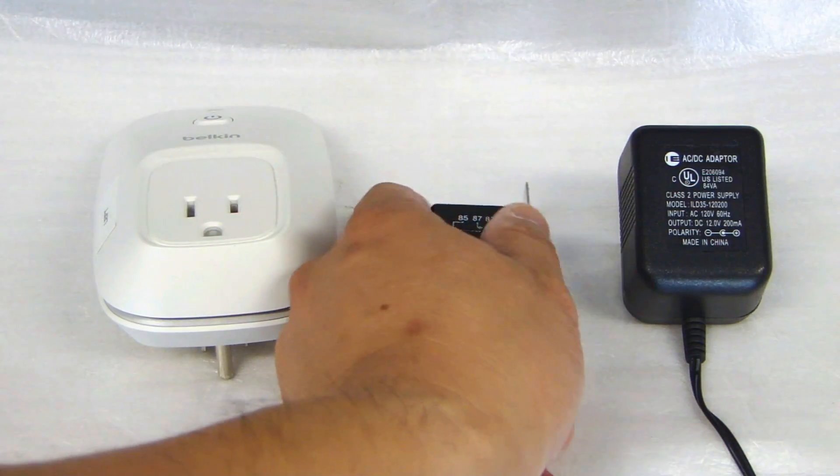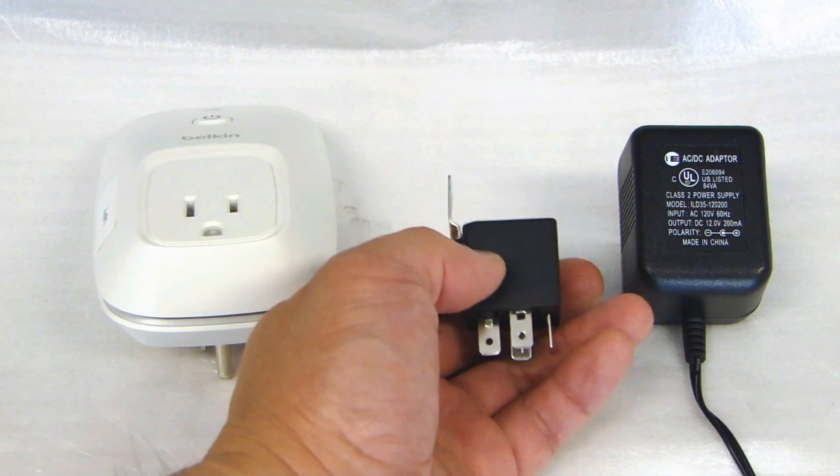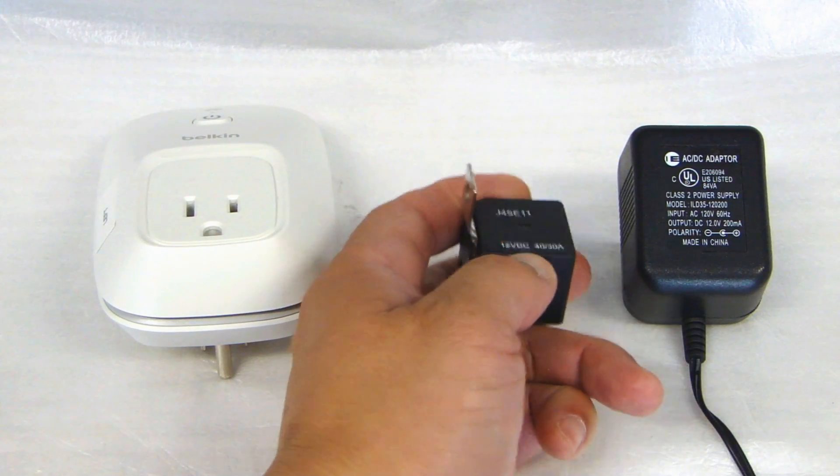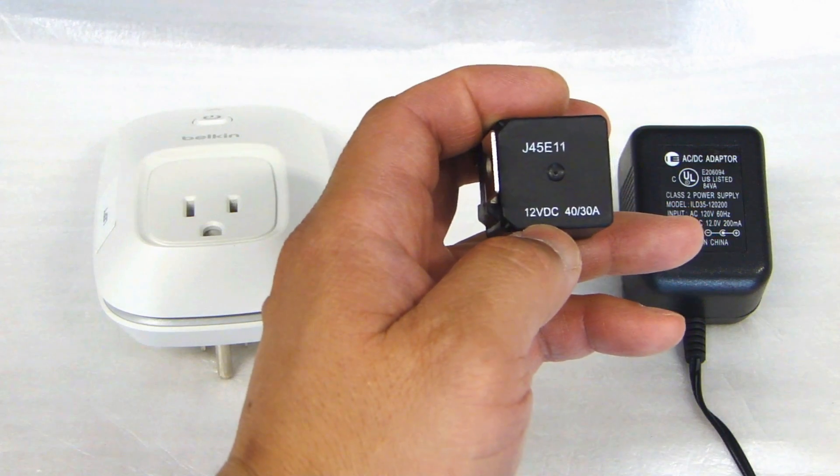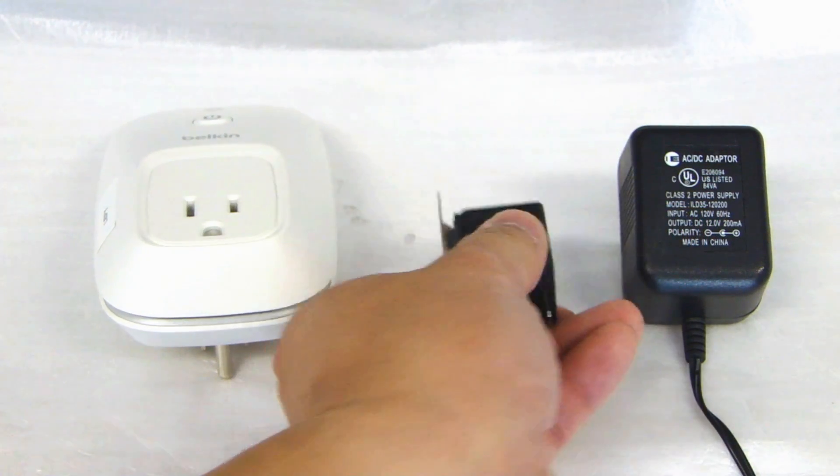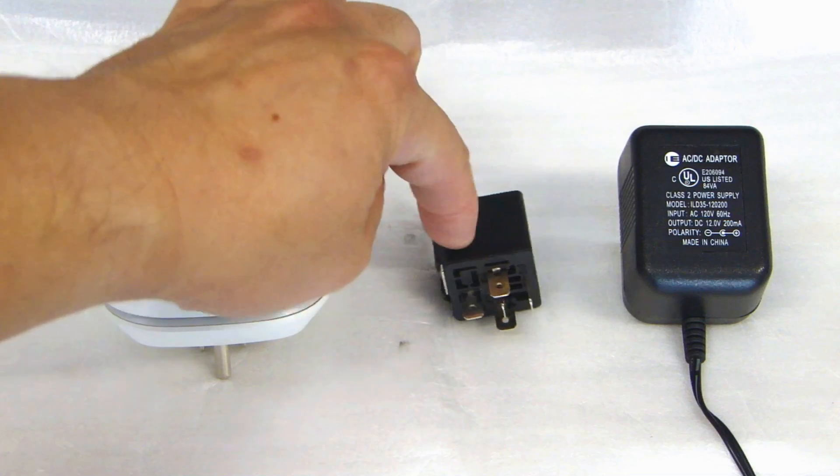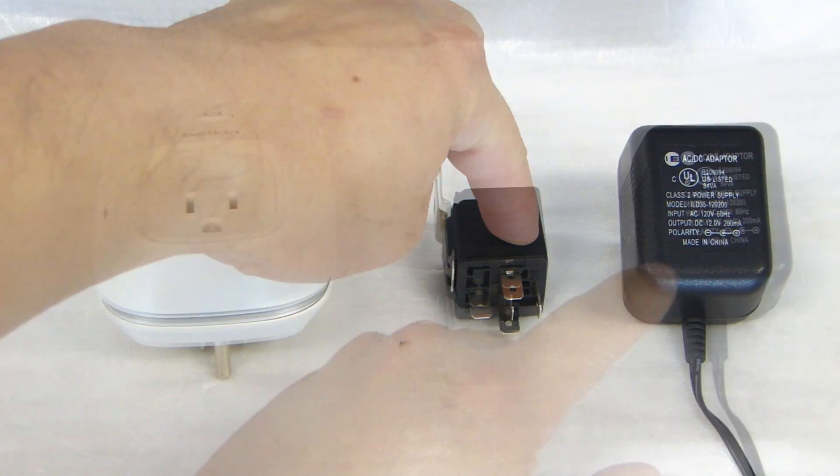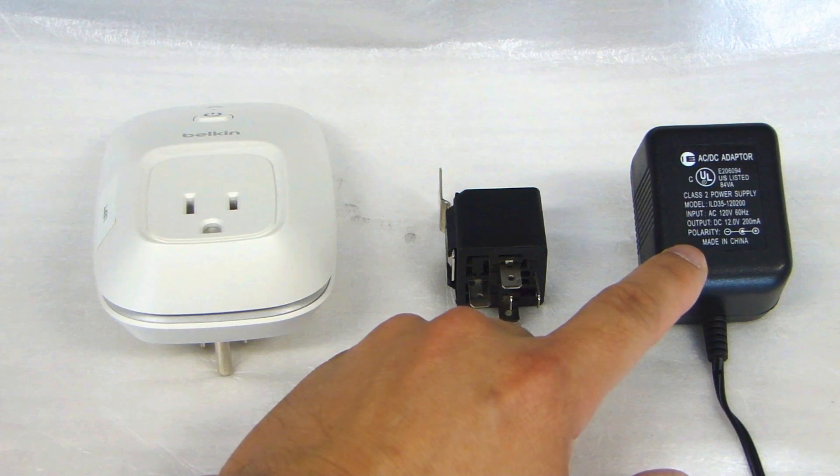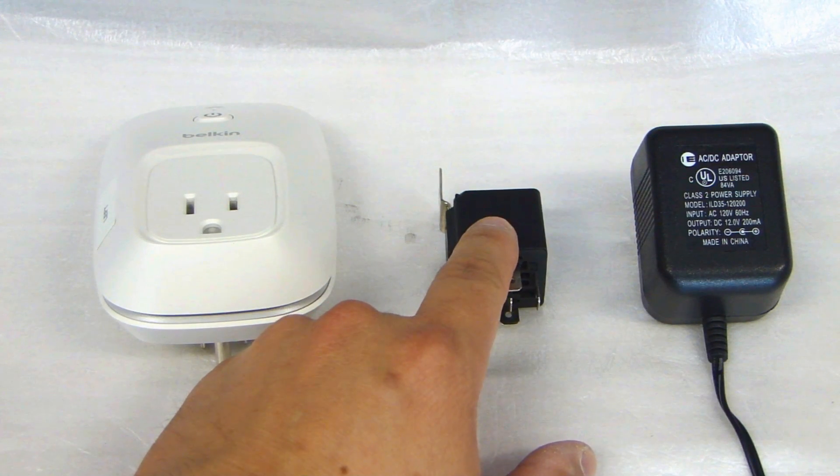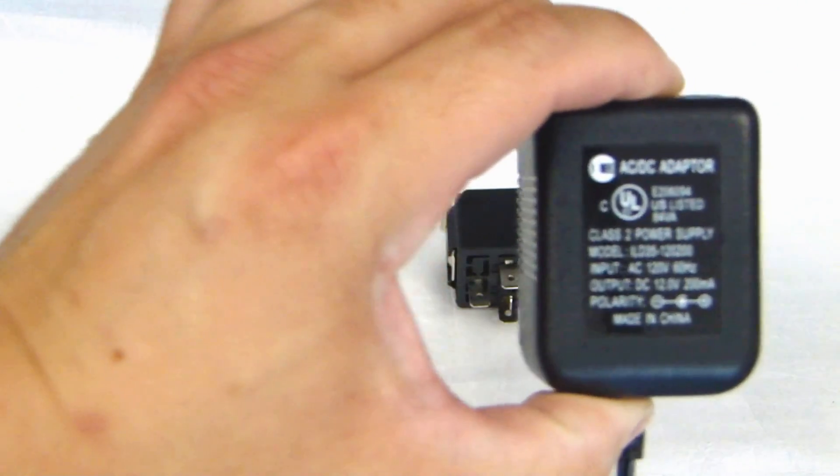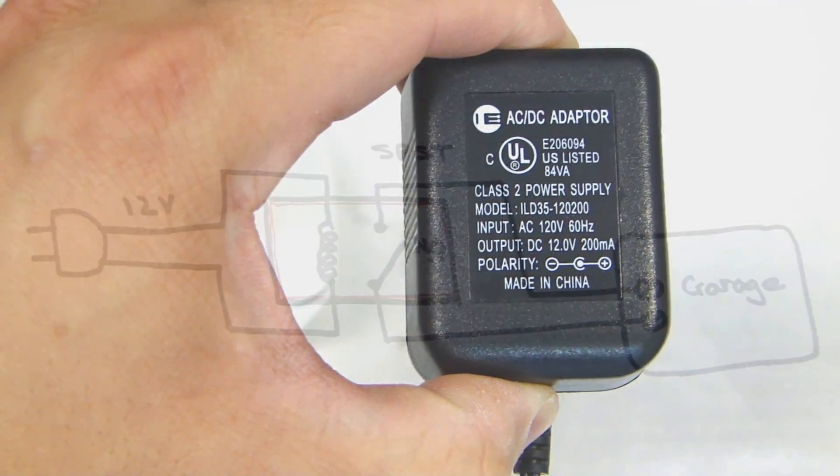Now, pay attention to the relay that you use because the coil side on the relay is rated for a certain voltage to energize. So right here, you see 12-volt DC. That tells you that this relay requires 12-volt power source to energize, so the internal switch will open and close. Here on the right, this is the power supply I'll be using to energize this relay. As I mentioned, this relay I'm using is 12-volt to energize the coil. So if you look at the output of this transformer, the output tells you that it outputs 12-volt DC.